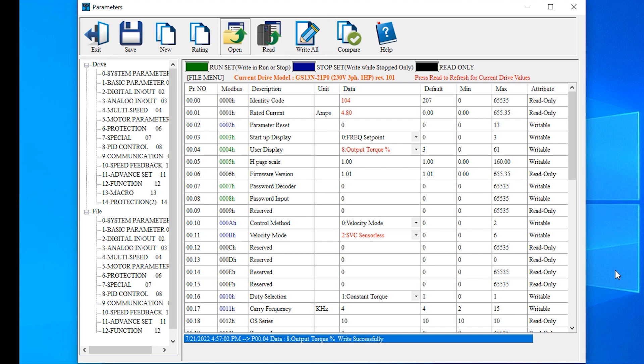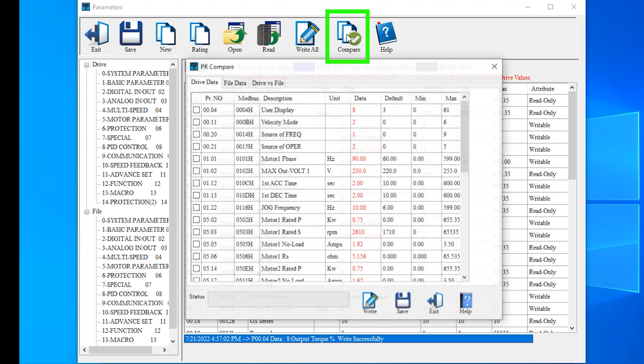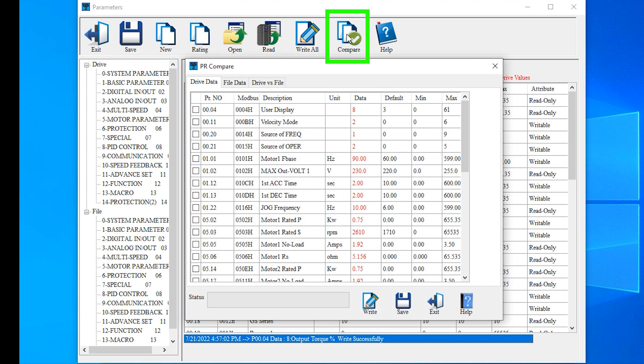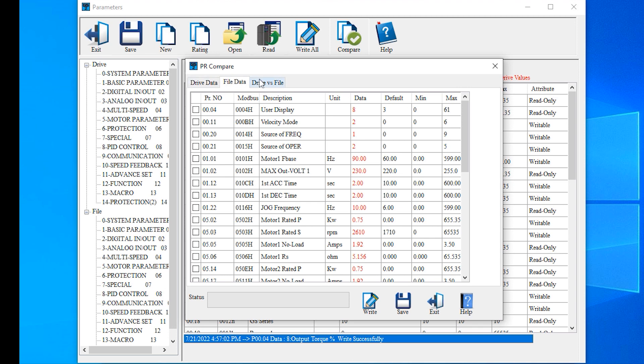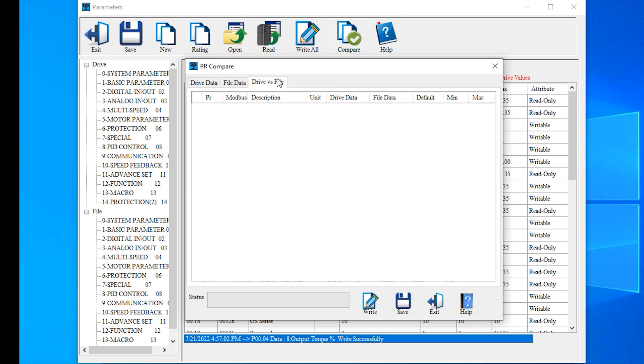Since this particular file should be what's on my drive, let's hit the compare button and see if it is. We have the drive tab and the file tab, which show all the parameters in each that are changed from default. Then we have the drive versus file tab, which shows any differences between the two. This comes up blank in this instance because they match exactly.